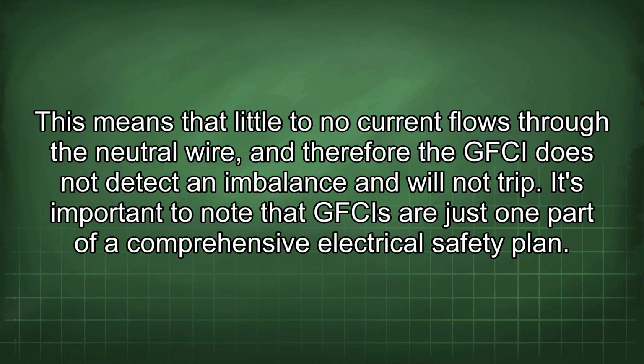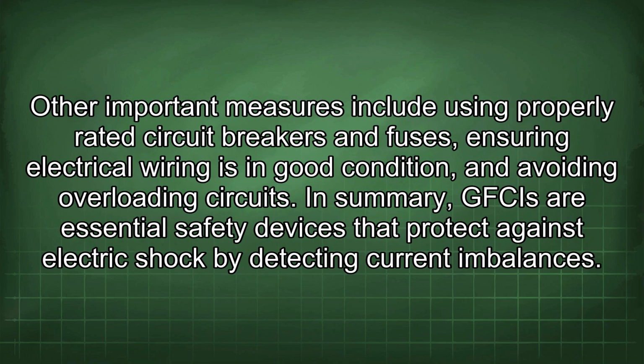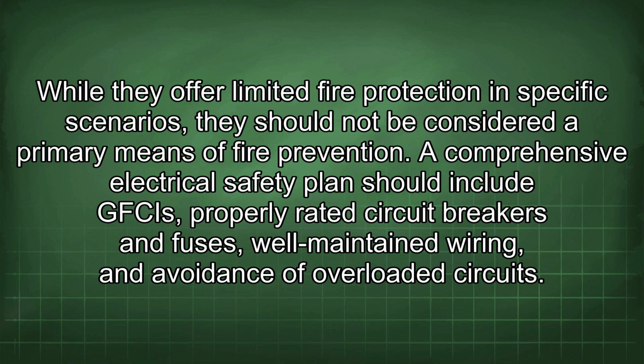It's important to note that GFCIs are just one part of a comprehensive electrical safety plan. Other important measures include using properly rated circuit breakers and fuses, ensuring electrical wiring is in good condition, and avoiding overloading circuits. In summary, GFCIs are essential safety devices that protect against electric shock by detecting current imbalances. While they offer limited fire protection in specific scenarios, they should not be considered a primary means of fire prevention. A comprehensive electrical safety plan should include GFCIs, properly rated circuit breakers and fuses, well-maintained wiring, and avoidance of overloaded circuits.